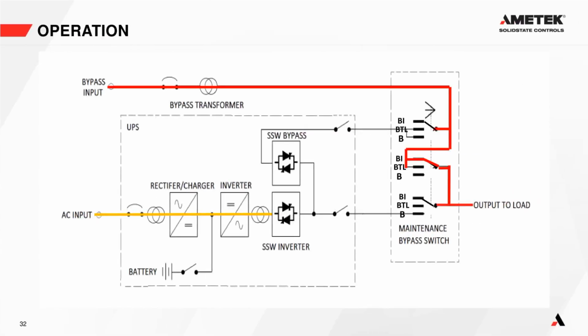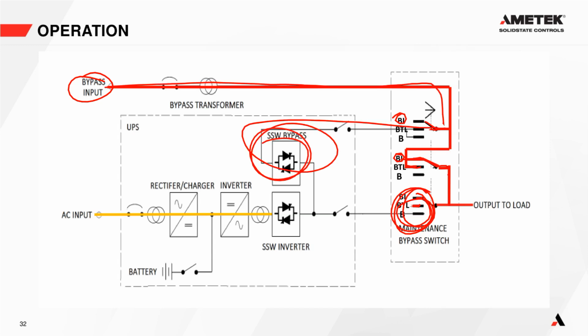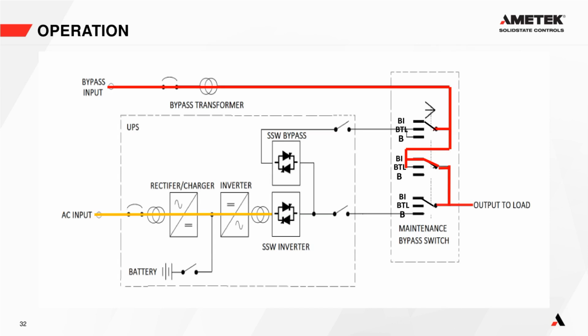And then the last position is the bypass isolate position. Okay. Once again, it's a make before break arrangement. And all it's doing is, nothing changes down here because we were at bypass to load before, and now we're at bypass isolate. So there is no connection at this point here. Now, rather than go through this bypass to load connection, we are now going through the bypass isolate connection here. But more importantly, at this bypass isolate here, there is no way now that the bypass input can get through here and get back to the static switch, okay?